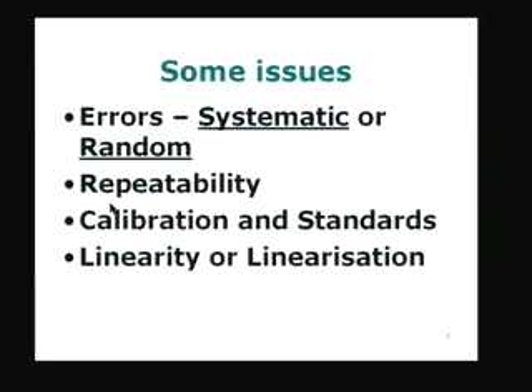In order to circumvent some of these things like systematic errors, we are forced to use a calibration. Calibration is a process of comparing a particular instrument with an instrument which is accepted as of good quality. So, calibration means comparing an instrument X with an instrument which is already available, which is already proved to be good, and somebody has given you a certificate saying that that instrument is good. Then you compare your instrument with the calibrated standard reference.